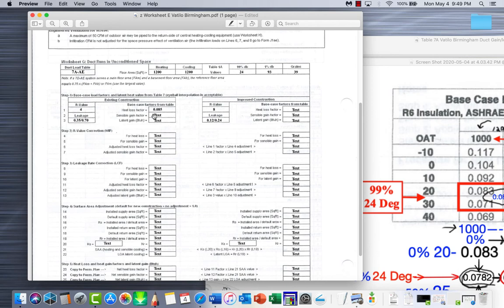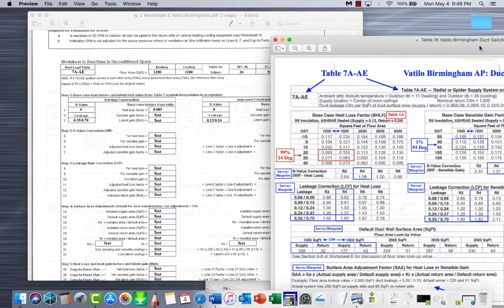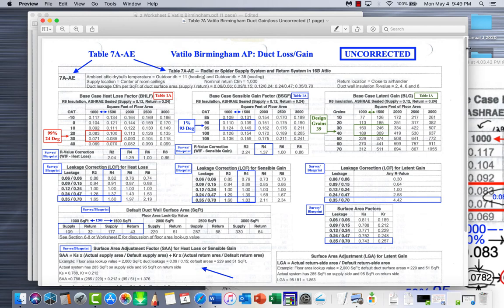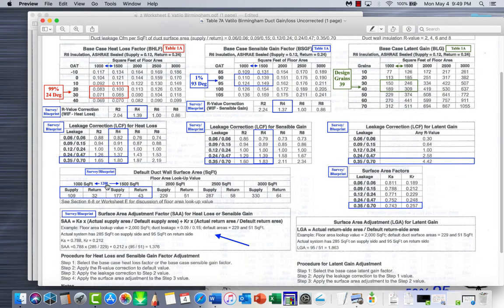To keep this video shorter I'll stop there. Now you know how to do the sensible gain and latent gain calculations. When we come back in the next video, those values will already be filled in using the same method. Then we'll move down to the R-value correction calculations, and you'll also run into the same split-difference interpolation when we get to the default ductwork surface area, since it's also between 1,000 and 1,500 square feet - 40% between those values on both columns.